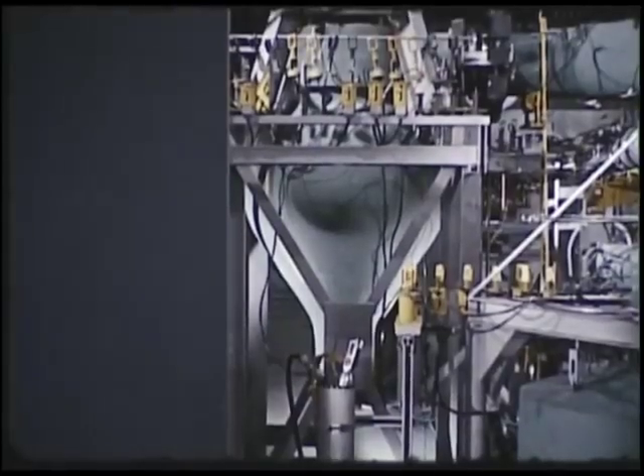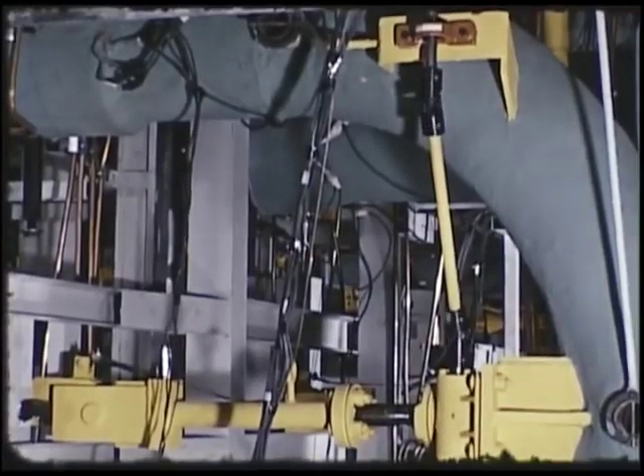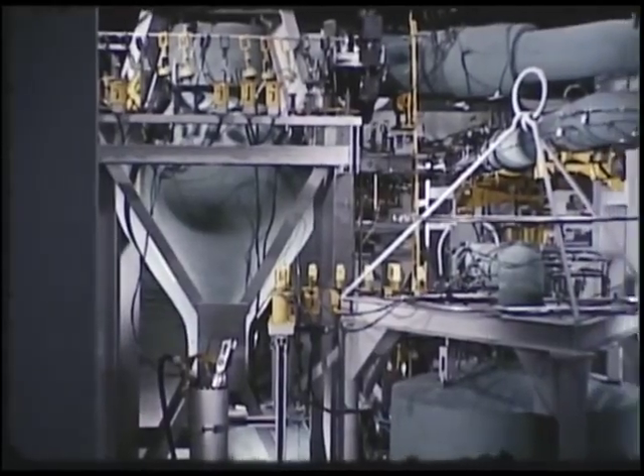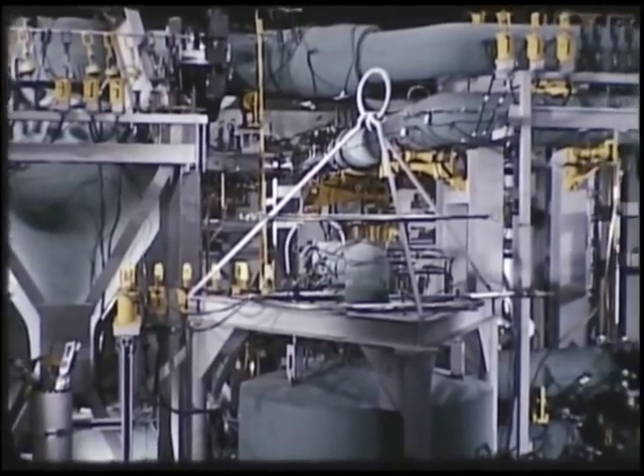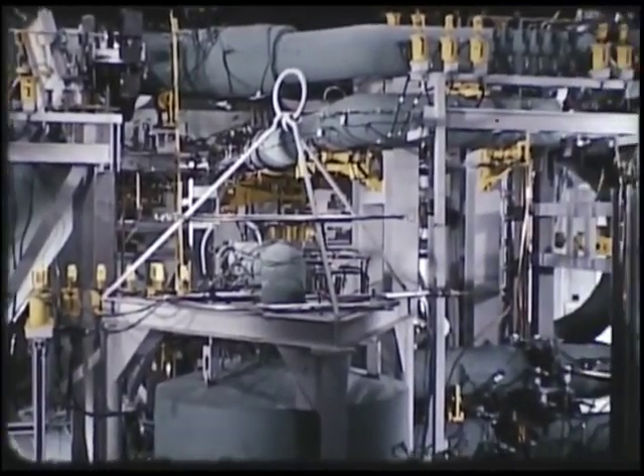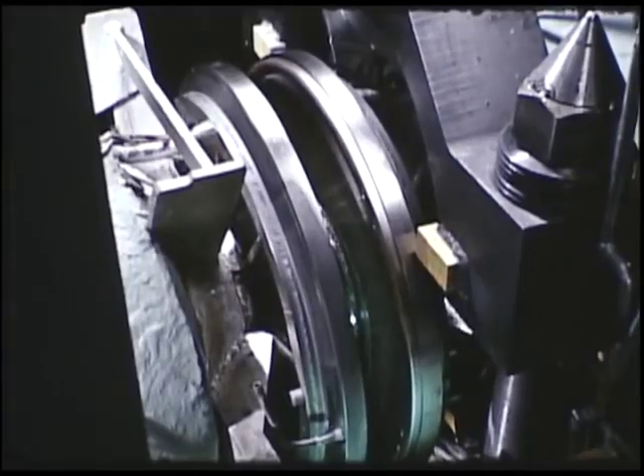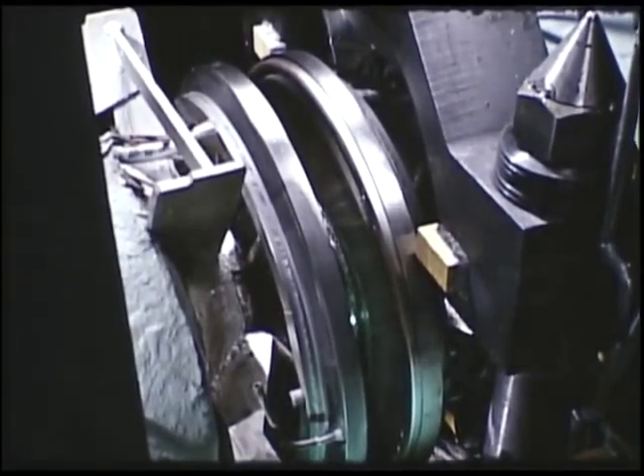The reactor remains stationary, while the screw jacks push the reactor piping system, including the heat exchangers, away from the core vessel. This is possible because the entire reactor piping system is floating and free within limits to move in any direction. Approximately 36 counterclockwise turns are needed to open a 2-inch gap between flanges.